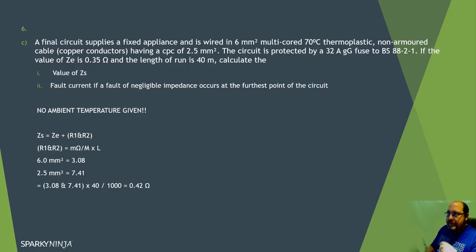Part C - the Zs calculation: the final circuit supplies fixed appliances with a 6mm² multi-core 70°C thermoplastic non-armoured cable, copper conductors, CPC of 2.5mm². It's protected by a 32 amp GG fuse to BS 88-2, Ze is 0.35 ohms, run is 40 metres. Calculate the value of Zs. No ambient temperature is given, so I can't verify whether I need to adjust the resistance values of R1 plus R2. Zs equals Ze plus R1 plus R2.